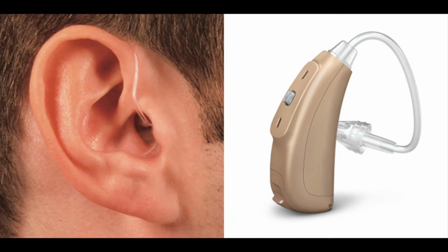Similarly, RIC and RITE hearing aids, receiver in the canal and receiver in the ear hearing aids, have to be cleaned by wiping off the piece that goes in your ear and changing the wax guards. The difference here is the piece that's behind the ear is where the majority of the electronics are. The only part that's electronic that's in the ear is indeed the speaker. So the cleaning, again, is very similar to the in-the-ear model, with the additional process of brushing off the back of the hearing aid itself, which is where the microphones are housed.